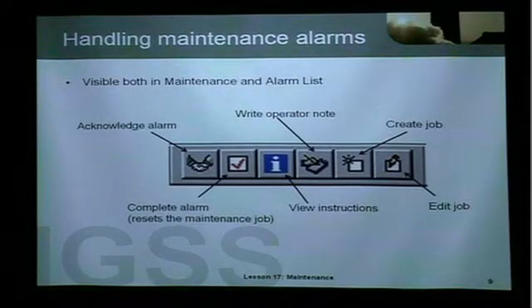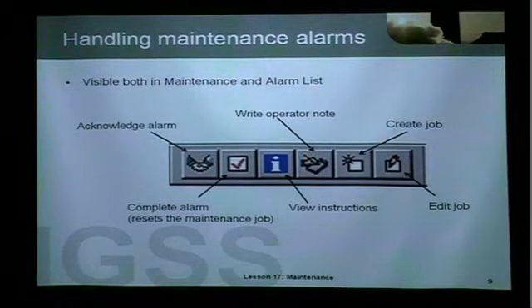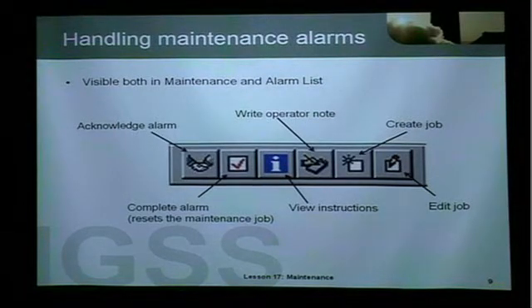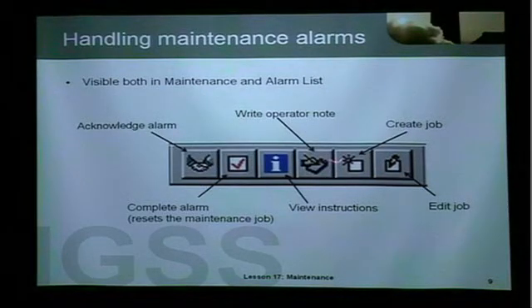When the operator sees a maintenance alarm, he can see it both in the maintenance and alarm list. The first thing he will do, just as with a normal alarm, is acknowledge the alarm — he can do this from either list. When he has done the physical maintenance job, he will go into the maintenance list and complete the alarm, which will reset the maintenance interval. If he wants to view instructions, he will click the info icon in the toolbar. He can also write an operator note. The person with the appropriate rights can also create or edit a maintenance job.